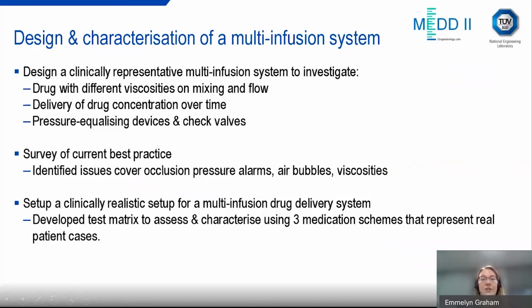This includes issues we've already covered, but also pressure alarms. If you get a blockage, an alarm will go off, which will highlight to medical staff that there is an issue. Air bubbles, viscosity effects. What we're looking at is what the effects of viscosities are on different mixing and flow, and also on the delivery of the drug concentration over time. We're also looking at pressure equalizing devices and check valves.